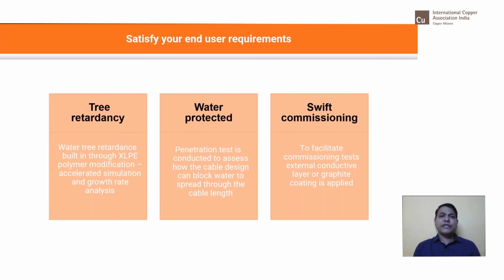So water protection is another thing which is quite popular again in Europe, the UK, and it should be in part of many areas in India, and it is quite popular in the Middle East because, being a desert, the water is just half a foot or 1 foot down. When the medium voltage cable is laid, it needs to be protected from water. So water block conductors or water block designs are used, so that they can block the water coming into the conductor or spreading through the cable length. So that is very important.